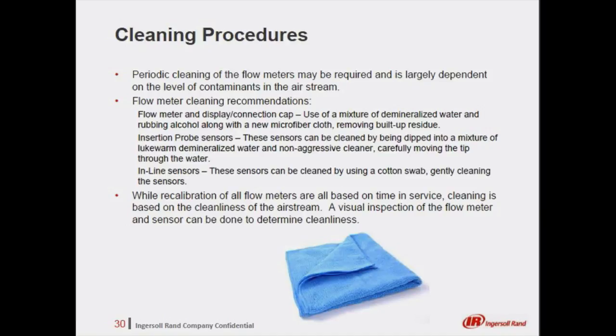Insertion probe sensors can be cleaned by being dipped into a mixture of lukewarm demineralized water and non-aggressive cleaner, then moving the tip through the water, but pay careful attention not to bang the sensors into the container walls. Inline sensors can be cleaned by using a cotton swab with the same lukewarm demineralized water and non-aggressive cleaning mixture, gently cleaning the sensors.